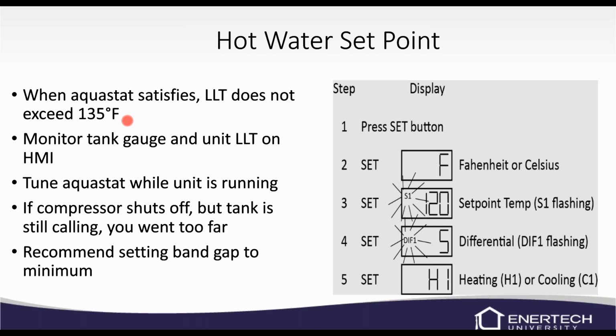So basically you're going to monitor the tank gauge and the unit leaving load temp on the HMI. And then you're going to tune the aquastat while it's running. So if the compressor shuts off and your tank is still calling, you've gone a little far with your set point. And we also recommend setting your temperature differential at a minimum, or your band gap. So we would recommend probably right around 5 degrees on that.